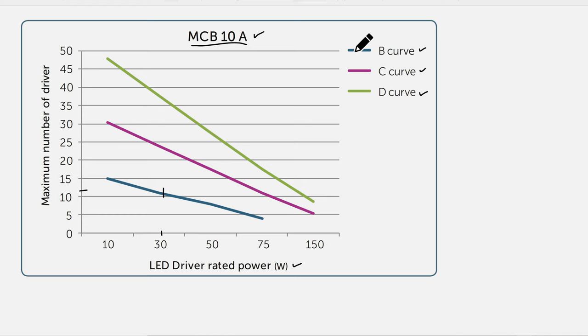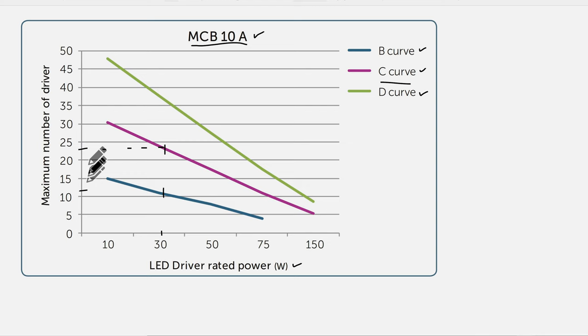Circuit breakers follow different tripping curves. If I used a C curve I would be able to have even more of those floodlights. For example, with a 10-amp circuit breaker following the C curve characteristics, instead of 11 floodlights I could possibly have 24 floodlights. Let's have a look at those tripping curves.